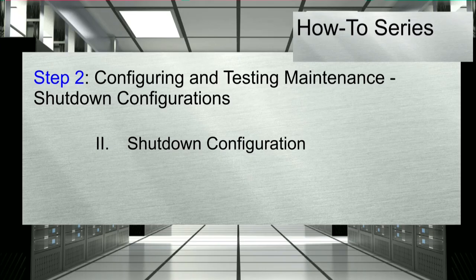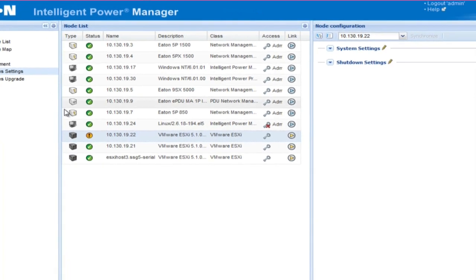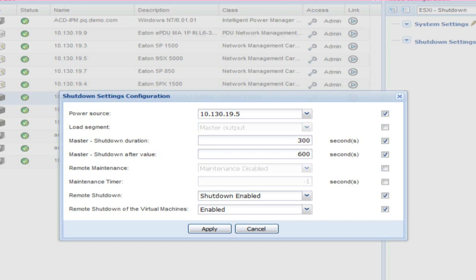2. Shutdown Configuration. Next, we will review the shutdown configuration. Once the UPS supporting the selected ESXi host experiences a power event, IPM will trigger the shutdown of the designated host. In order to set the parameters, start from the IPM view screen. Select the folder titled Management and click on the option for Node Settings. Choose the VMware ESXi host that you would like to configure. Once selected, the Node Configuration pane will open to the far right of the screen. Click on the pencil icon beside the option titled Shutdown Settings. The Shutdown Settings configuration text box will appear. The parameters selected will enable IPM to take action with the designated escalation mode.